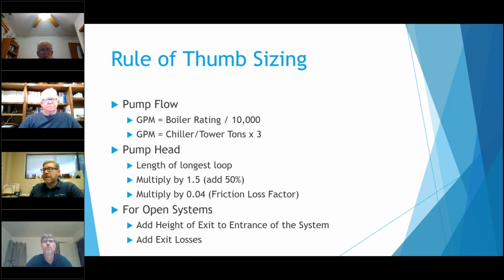And then you multiply by a friction loss factor. 0.04 is what I typically use. It is on the very high end of the scale, so there's a lot of extra safety built into it, so that you don't underestimate the head when you're just trying to guess what it is. But 0.04, like I said, is on the high end. You could get it a little bit higher if you're trying to flow more water through a piece of pipe, but there's usually a range you want to try to maintain. And that 0.04 is right there at the top end.